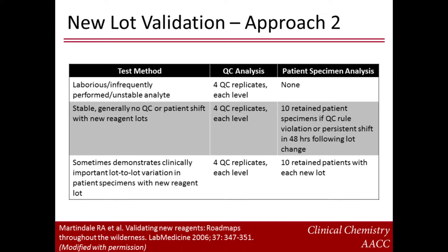Examples of such tests in the first group include ACTH, bile acids, fecal fats, and tissue copper. The recommended approach for this group is to collect four measurements per QC level with the new reagent lot. Troubleshooting follows any out-of-range results or the discovery of QC shifts exceeding one standard deviation. The second group of tests includes those that rarely show lot-to-lot variation for either QC or patient results. Patient comparisons should only be performed for tests in this group if the initial QC measurements violate error rules or if a persistent shift is detected in the 48 hours following a lot change. The third group includes tests that in the past have demonstrated large lot-to-lot variations in patient results. HCG and troponin are good examples. The recommended approach for this group is to analyze ten patient samples with the old and new reagent lots, regardless of the results of initial QC measurements.